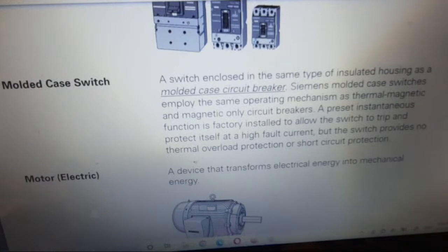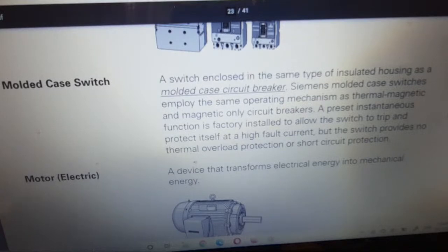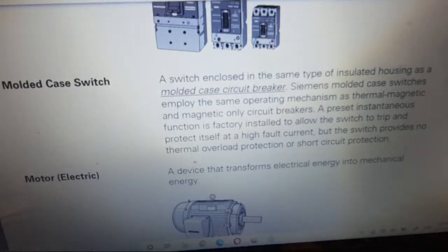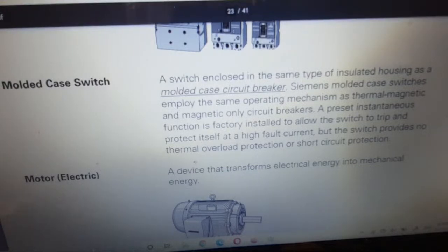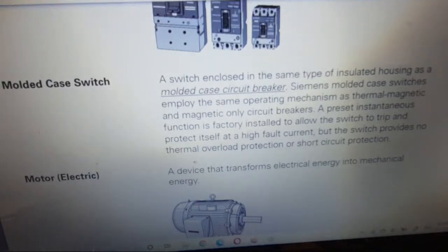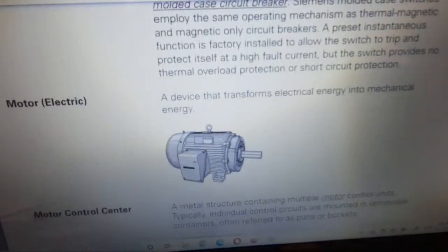Molded case switch: a switch enclosed in the same type of insulated housing as a molded case circuit breaker. Siemens molded case switches employ the same operating mechanism as thermal-magnetic and magnetic-only circuit breakers. A preset instantaneous function is factory installed to allow the switch to trip and protect itself at high fault current. But the switch provides no thermal overload protection or short circuit protection.